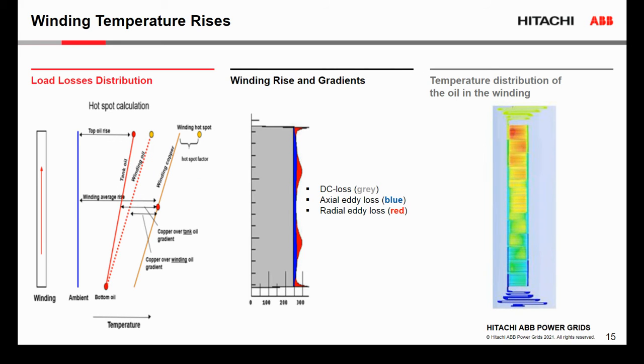Now, the winding temperature rises. How does the temperature of the winding change with the height of the winding? On the bottom of the tank, the temperature of the oil in the tank and oil in the winding is pretty much the same. But when we go to the top, the tank oil temperature is several degrees lower than winding oil temperature. It is because the winding oil temperature is next to the source of the heat, which are the windings.